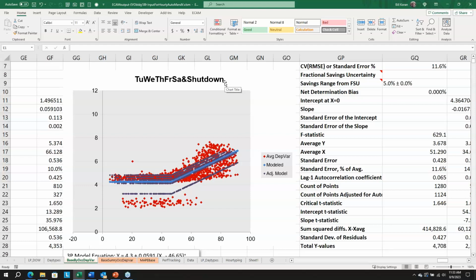The other thing to know is that segmenting the data into those periods is actually quite robust in ECAM, because it's done in a brute force manner where every grouping for 4 time periods in a day, ranging from 1 to 19 hours long, is examined and checked for how well it fits the actual data. Every possible combination is examined. You could have unoccupied for 1 hour in the morning, startup for 1 hour, occupied for 1 hour, and then unoccupied for 19 hours in the afternoon - it'll check that. Or conversely, it could be 4 even 6-hour periods for the 4 time periods.